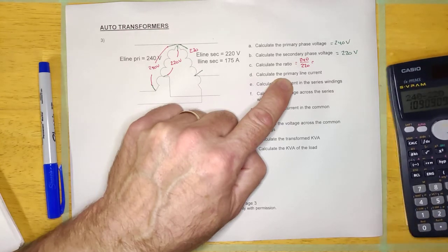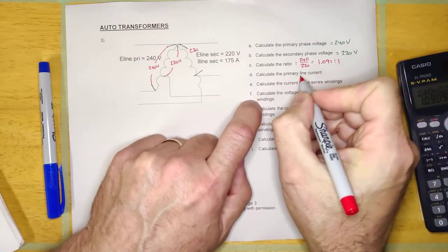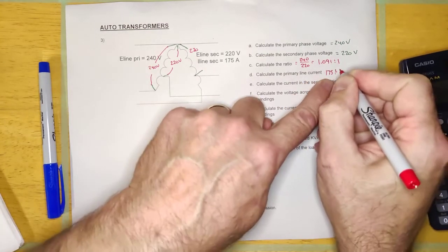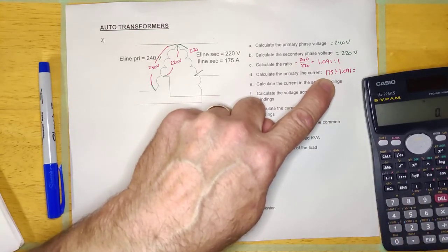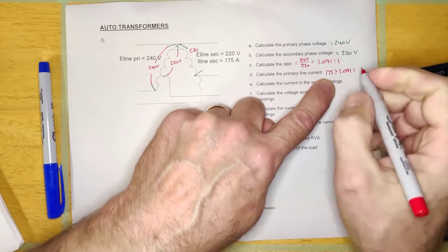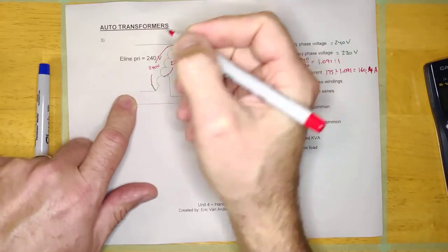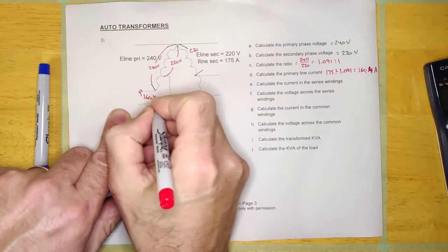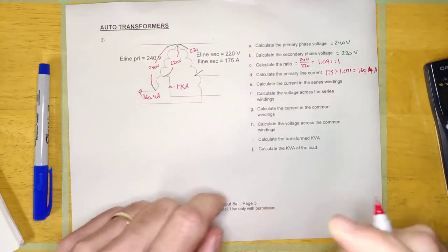Calculate the primary line current. We're going to do it exactly the way we've been always doing it. It's going to be the secondary current, 175 amps, divided by the ratio. That'll work for every kind of transformer - single phase, Y, or open delta. 175 divided by 1.091 equals, looks like that current is 160.4 amps, and we're going to put that right on here so that we can figure it out later. This one right here is the 175 amps, the secondary line current. That's going to help us figure out what's going on.